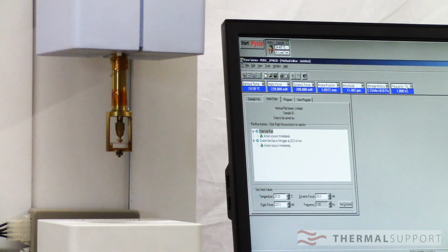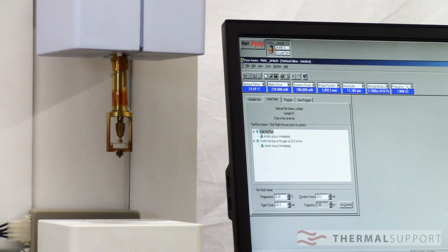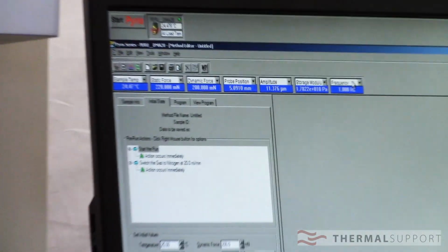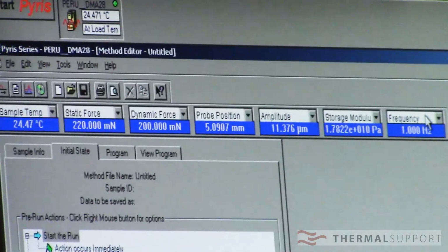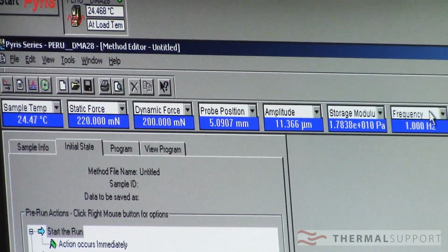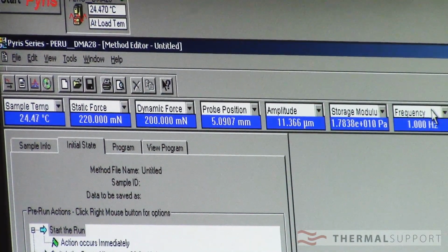And that gives us about 11 microns amplitude. That gives you plenty of data points to work with. And I don't know if you can see the screen. The screen's coming back 1.77 to the 10th PA. So it looks good. The instrument looks great. The only other thing to do is just simply do the calibration.